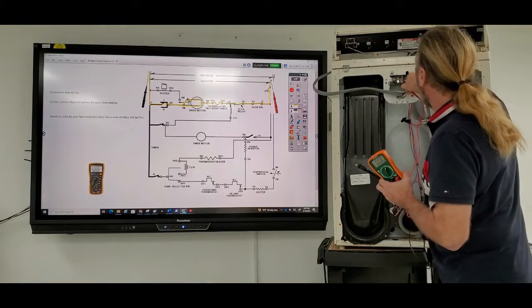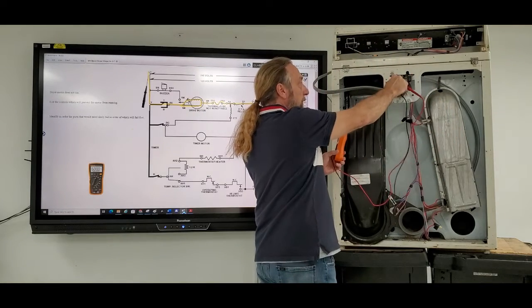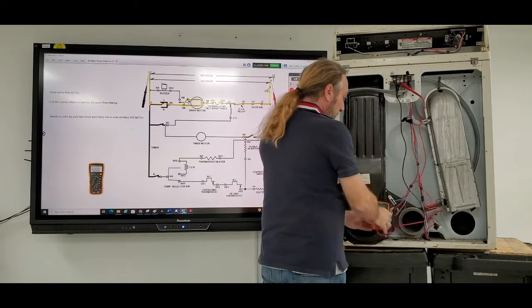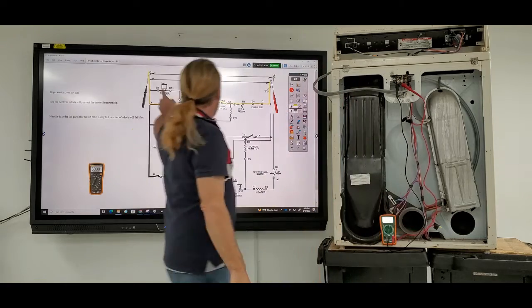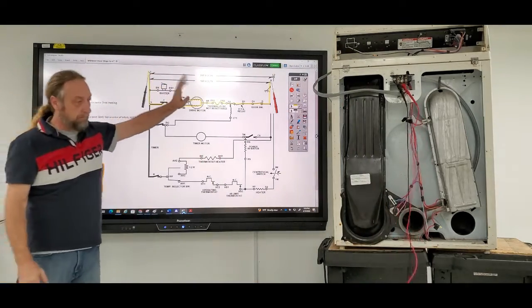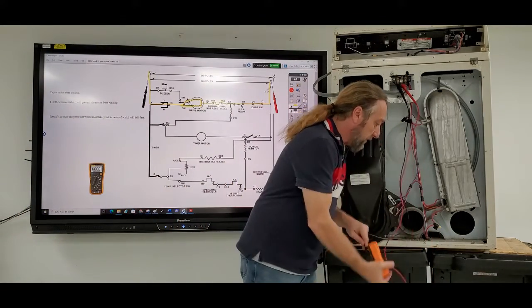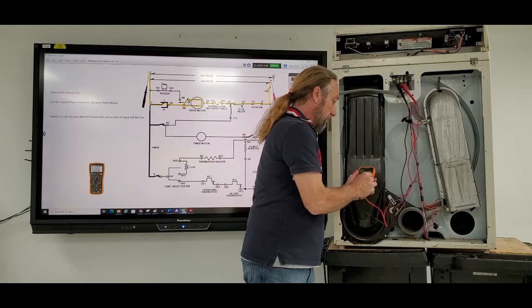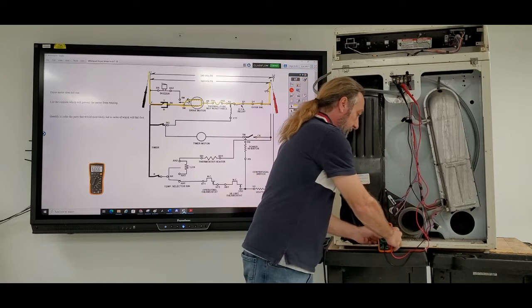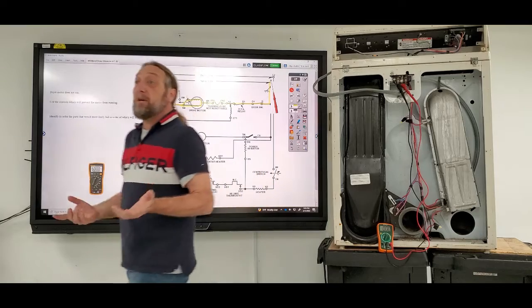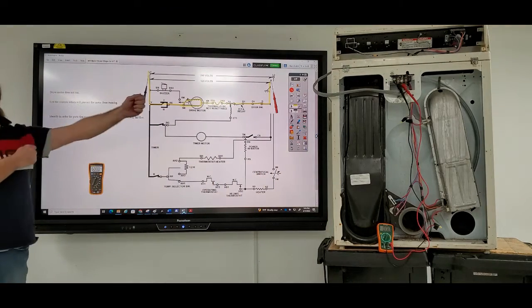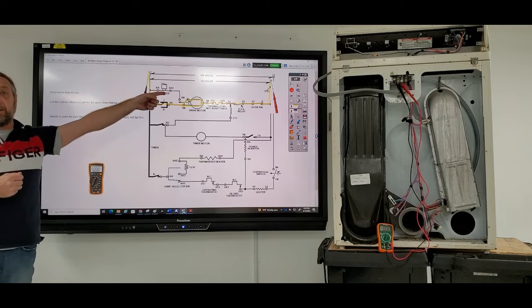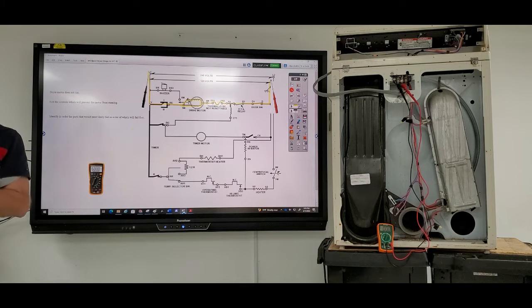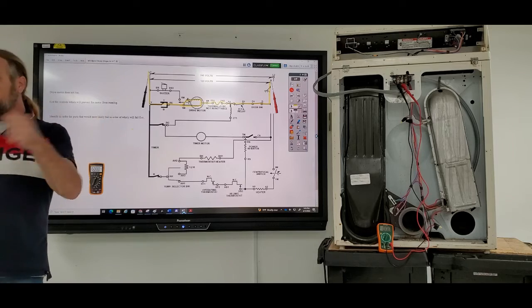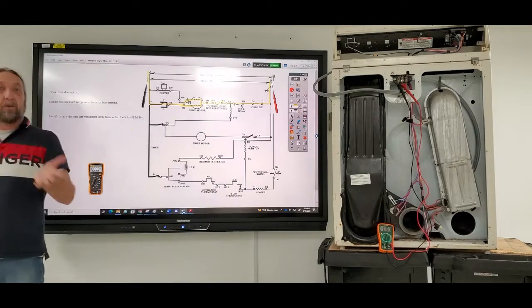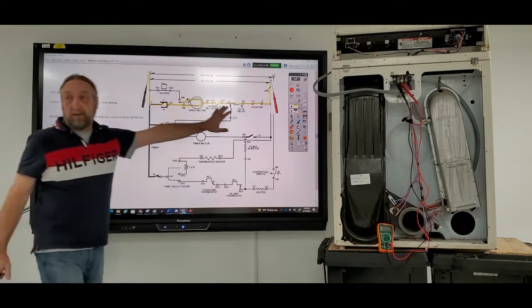So we're going to check neutral here and line 1 like this. And I have it just like the picture, where the black meter lead is on line 1 and the red meter lead is on neutral. Does it matter in AC voltage if I had them reversed, if I had the red meter lead here and the black meter lead there? No. It does matter on DC voltage, but on this machine it doesn't matter the polarity of the meter, because either way it's going to read that voltage. So that's the test.